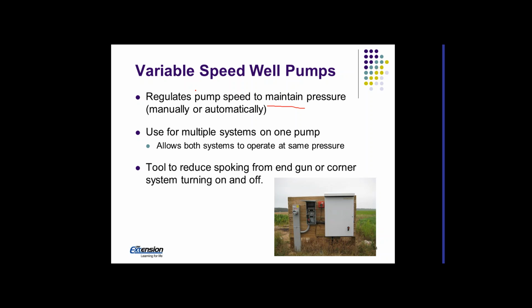This is particularly useful on irrigation systems where we have multiple systems on one well. So in most cases, when we do that, they're not going to operate at the same pressure, but with a variable speed drive, we can make that happen, and in the process we can save energy. The other is we can reduce spoking or non-uniform application of water because of changes in pressures from end guns and corner systems turning on and off.